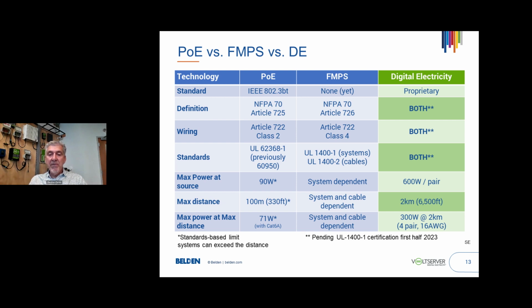90 watts, as we mentioned, on PoE. Fault-managed power systems, because of that thing that I mentioned, where the source of electricity is rendered to be safe at the source, at the transmitter, it doesn't really have any technical limit. It is limited in voltage, so the standard would go up. It supports up to 450 volts DC, the new 1400-1 standard. So anything that you could get under DC power at that voltage level is sort of game. I mean, the cables, the different manufacturers will be making different gauges to support those power levels. But right now, digital electricity is roughly 600 watts per pair at nominal distances.